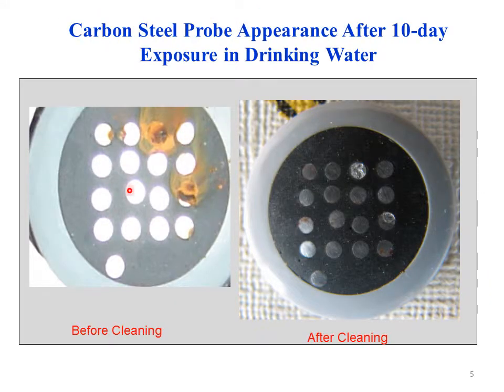On this slide, a carbon steel CMAS probe is depicted that has undergone localized corrosion from exposure to drinking water for 10 days. Corrosion product can be seen on these electrodes, and after cleaning, pitting can be seen on the corresponding electrodes due to the localized corrosion.